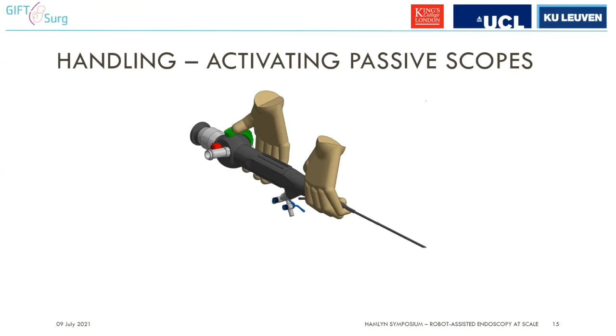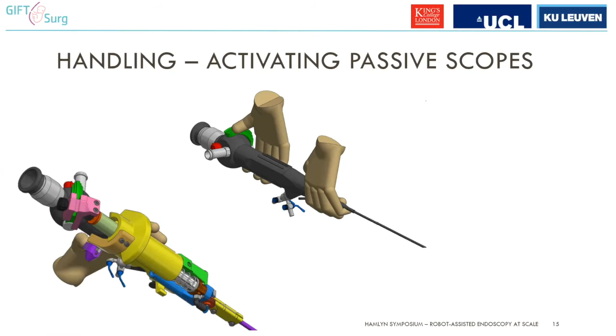And so that's a design that we had here, whereby this was realized by having one artificial muscle embedded, connected to the lever here, and a surgeon would be pushing on a button and then the lever would be moving back and forth. You may wonder, why is that needed? Well, in these fetoscopes, you have a laser fiber that is very stiff and that requires quite some force to manipulate. So if we would put the laser fiber straight in this instrument, the surgeon would need to apply quite some force on the lever, which would be tiring and in the end make it difficult to control precisely the position of the laser without too much tremor.